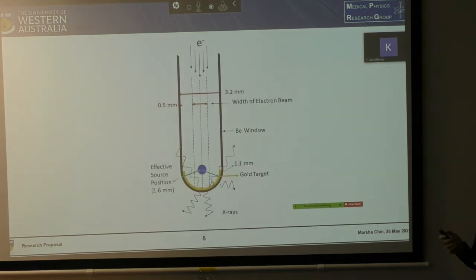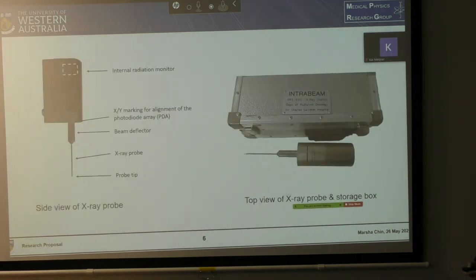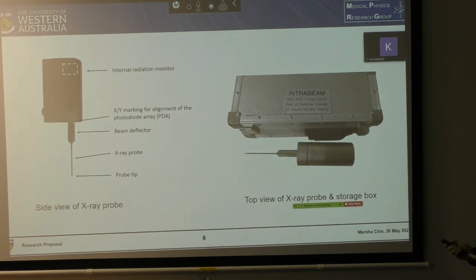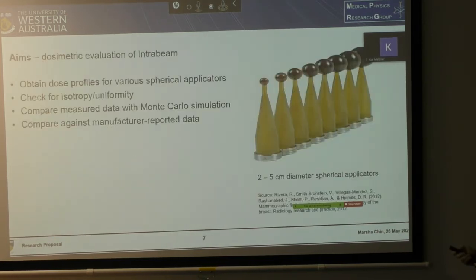So this is just a close-up of the X-ray production process. So you've got electrons coming down, they will hit the gold target here. And outside you've got a beryllium window, and beryllium is transparent to X-rays. This is a diagram of the actual device that we'll be using that we took photos of. Something new here is the photodiode array, which sits in here somewhere. So it helps measure dose isotropy and it will tune the electron beam if it needs to. And this is just the box that it comes in, the top view of the X-ray probe.